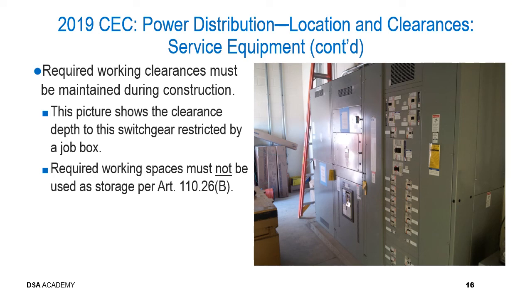Additionally, there's another article in the California Electrical Code, Article 110.26(B), which also stipulates that required working spaces must not be used as storage. So it's important that you're aware of this and also keep an eye out for this during construction, and remind the contractors of how important it is for the safety of their personnel working on this equipment that the required working spaces are maintained during construction.